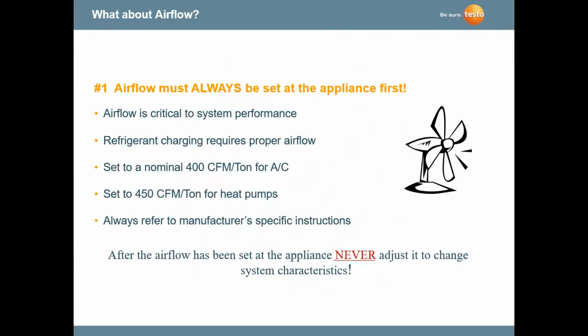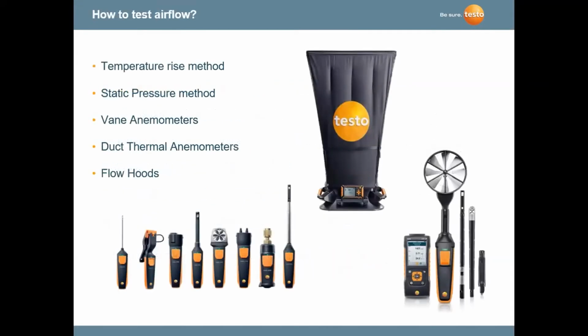Before we do any type of charge or maintenance on the system, airflow has to be measured. Typically, it's one of the first things that are measured, and we're setting the airflow over the coils to a nominal 400 CFM per ton on AC equipment, maybe 450 CFM per ton on heat pumps. That may change a little bit because of the conditions in Florida, and that's why you want to refer to the manufacturer's specifications on the amount of airflow for their equipment. And there are ways of looking at airflow. You've seen these instruments before, I'm sure, but the propeller type instrument is a vane anemometer. It measures feet per minute. There's differential pressure for a static pressure test. There are duct thermal anemometers that go inside a hard duct to traverse the ducts. And there are also flow hoods that are used a lot in the commercial market for test and balancing.